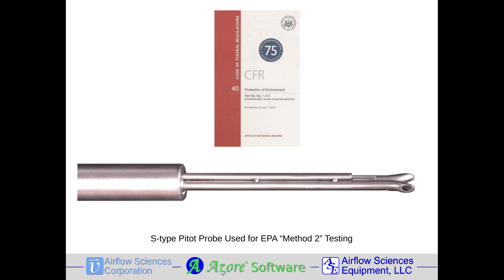Though there is a standard design for the S-type pitot probe, minor variations in manufacturing tolerances and wear over time can cause the probe measurements to vary. EPA Method 2 thus provides guidelines on how to perform regular calibration of a probe in the controlled environment of a wind tunnel. With the proper calibration, the most accurate flow measurements are obtained in the gas streams of ducts and smokestacks at industrial sites.